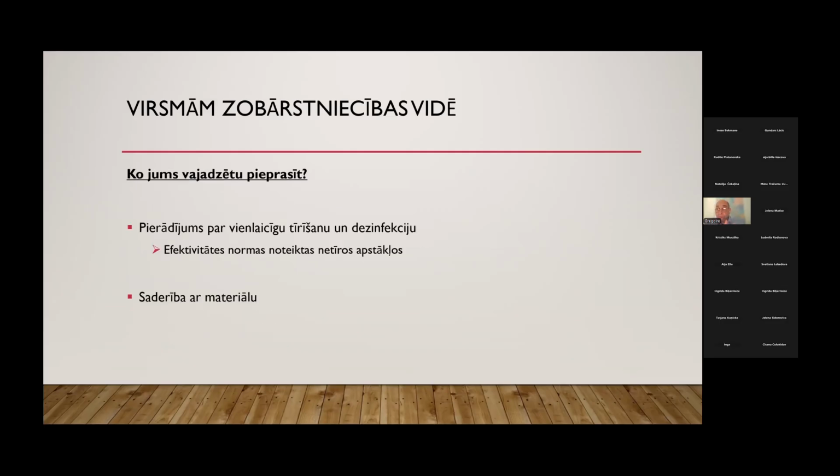So what should be requested from your side? As a dental cabinet, you should ask a stomatologic cabinet, you should request: I want the proof of detergent and disinfection at the same time. So I want to see efficacy norms in dirty condition. Remember, we said that the norms are here to make sure that the end user and the producer are talking the same language, especially in a case a third party is coming to check, then everyone is on the same page and everyone is safe. So this is very, very important.